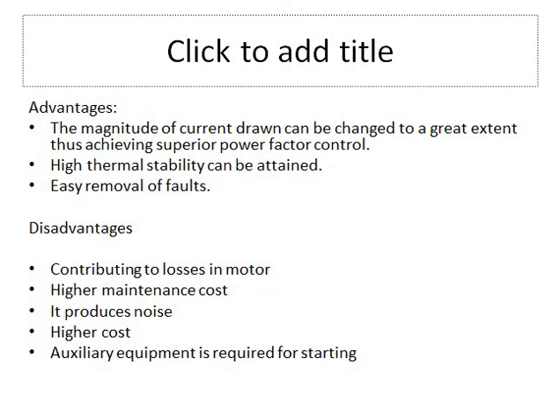Disadvantages of the synchronous condensers include losses in the motor, higher maintenance cost compared to the capacitor banks, and noise as discussed earlier. The cost is also very high, and further they are very large equipment, and auxiliary equipment is required for starting. So these are some of the drawbacks of the synchronous condensers.